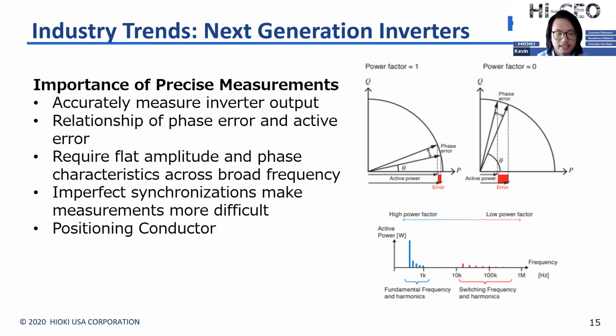So in order for us to take good measurements, we also need to have good sensors that are capable of measuring active power - not only for the high power factor fundamental wave and its frequencies, but also the low power factor for the switching frequencies and its harmonic components.